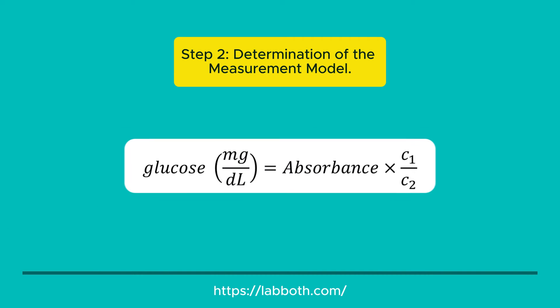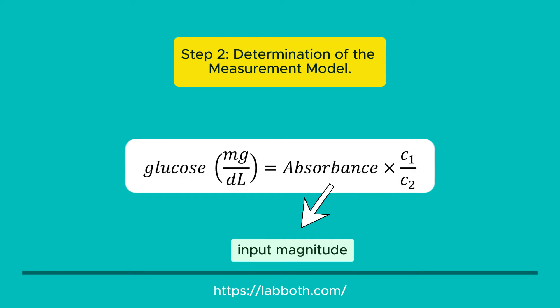Step 2: Determination of the measurement model. Associate your measurement result with a measurement model that takes into account the input variables. This model relates the output magnitude — the result of your assay — with the input magnitudes. An input magnitude, in the case of the glucose test example, could be the measured absorbance. This absorbance is multiplied by other input magnitudes to obtain the output magnitude, or measurement result: glucose concentration expressed in mg/dL.